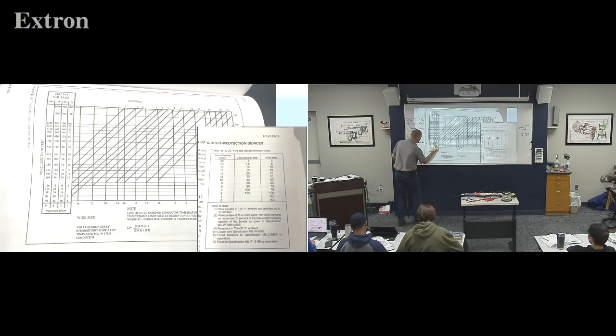So we're down to 12, 20 amps. Over here, it's that one, this one. Okay, coming over 12. Well, if that line were to continue, it would intersect me right about here. And okay, I need an 18 or a 20 gauge wire. I'll go with the bigger wire, which is a smaller number. Okay, I need an 18 gauge wire because it's really short. I'm only going a little bit of distance. So to have my allowable 2 volt drop, 18 gauge wire.